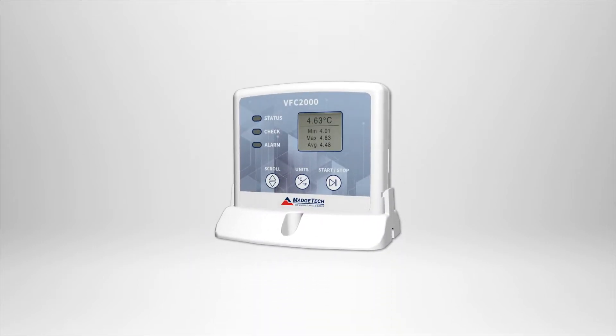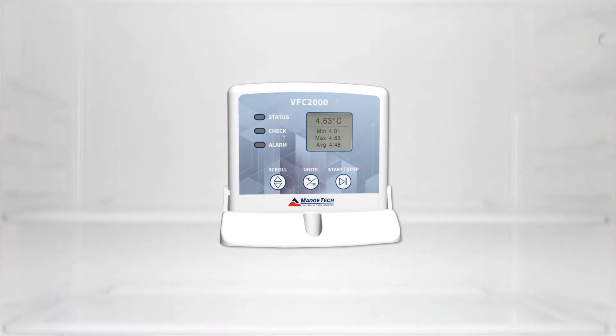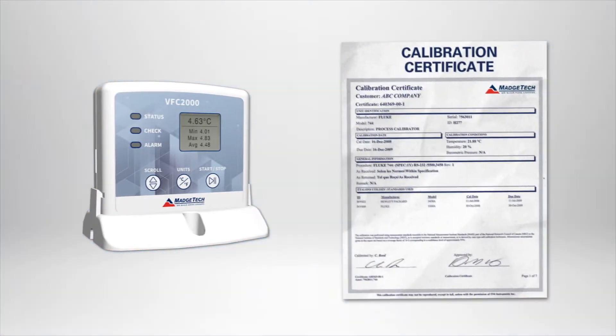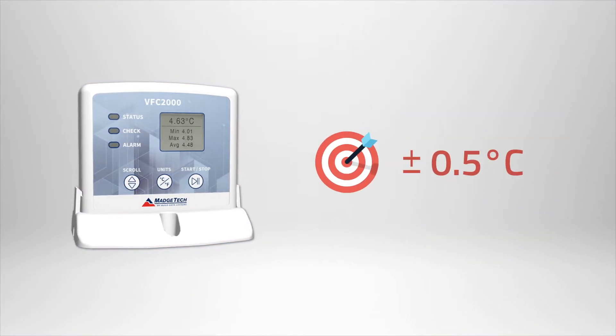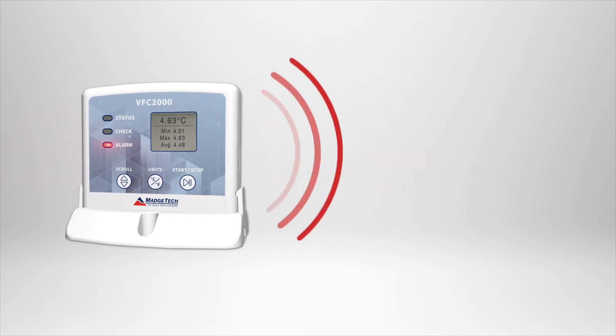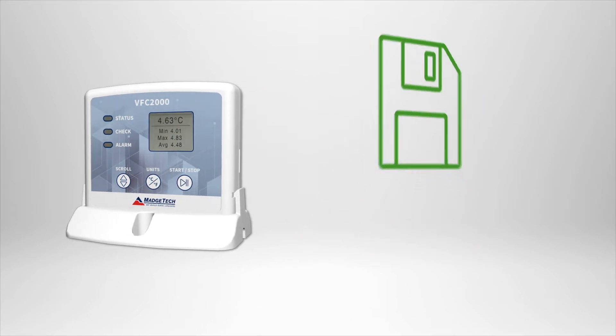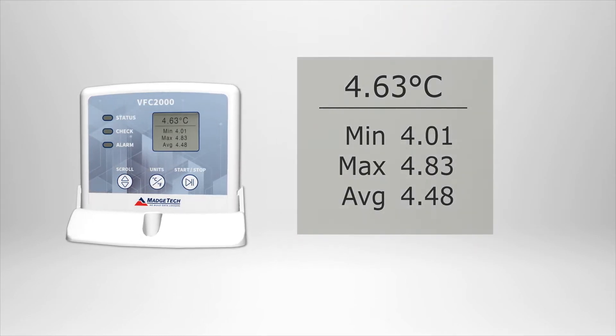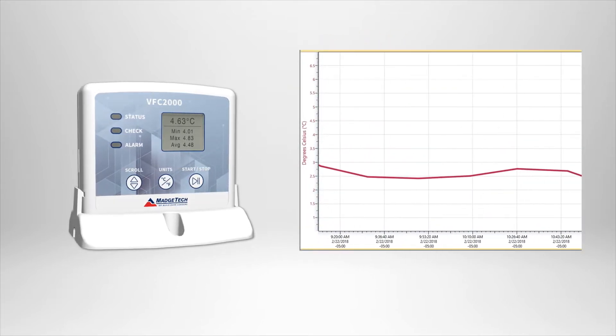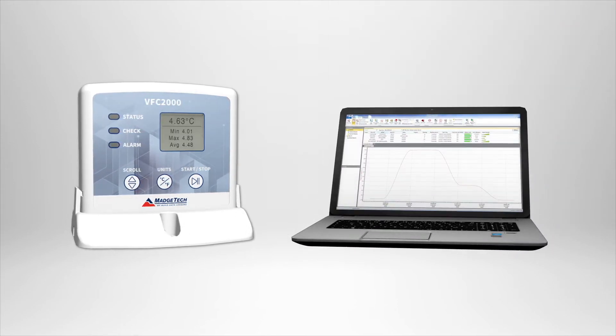The MadgeTech VFC2000 complies with or exceeds all of these set requirements, which include device calibration for both refrigerator and freezer use, a certificate of calibration, an accuracy of plus or minus 0.5 degrees Celsius, threshold alarms, a minimum of a 4,000 reading memory, visibly displayed current, minimum, and maximum temperature statistics, a user programmable reading interval, a buffered temperature probe, and data reporting capabilities.